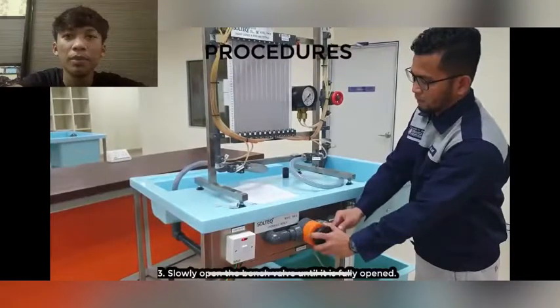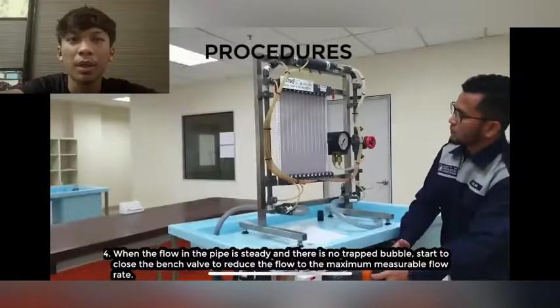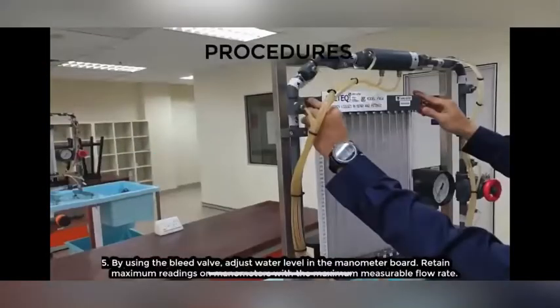The third step, slowly open the bench valve until it is fully open. The fourth step, when the flow in the pipe is steady and there is no trapped bubble, start to close the bench valve to reduce the flow to the maximum measurable flow.